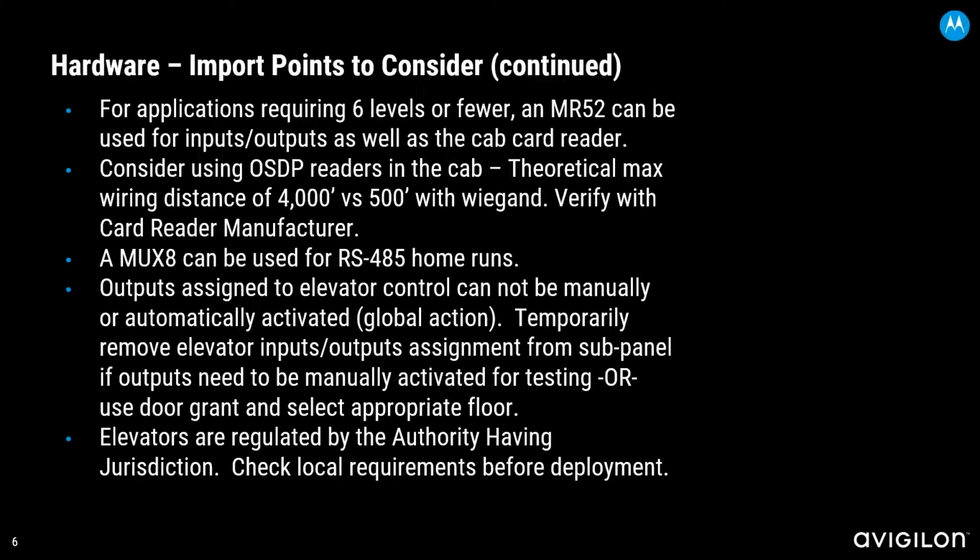In those scenarios, you have to put the equipment outside of the elevator control room and then run your output cabling back to the elevator control room. So typically, something else you run into, you all, unless you're a certified elevator service company, you can't do any work inside the cab itself.